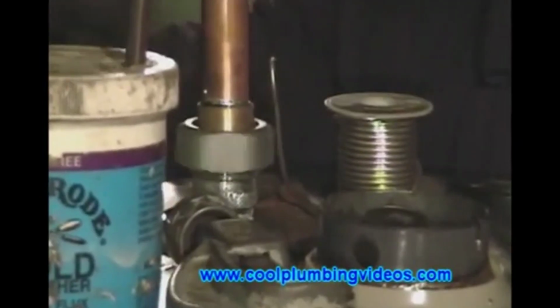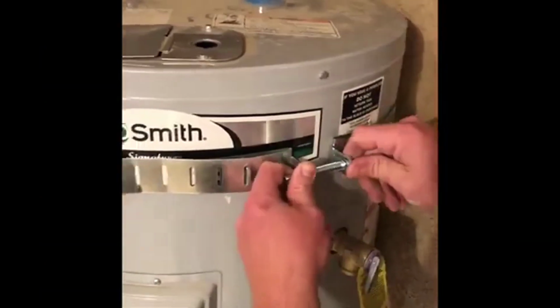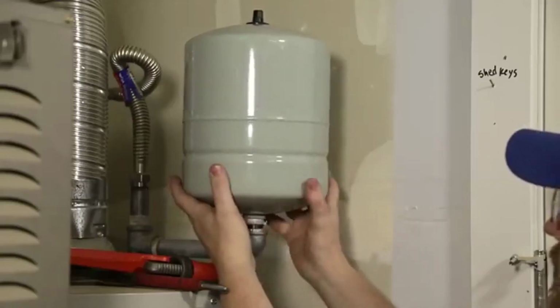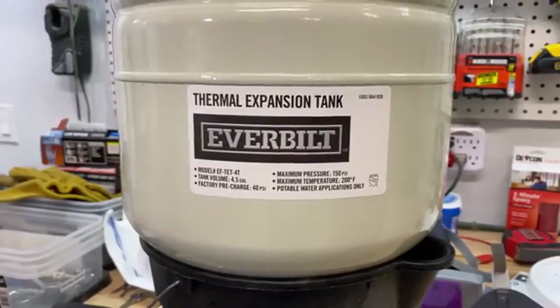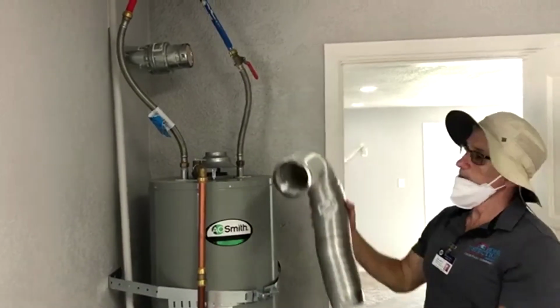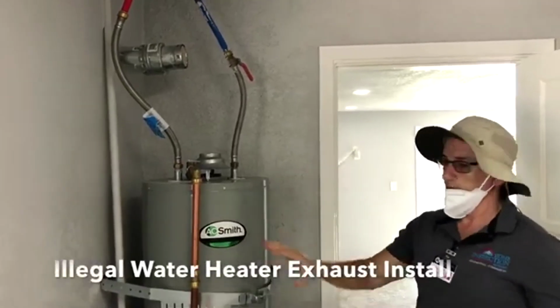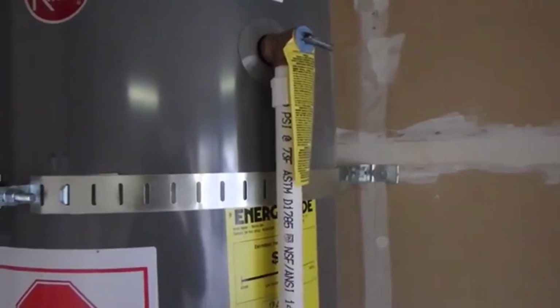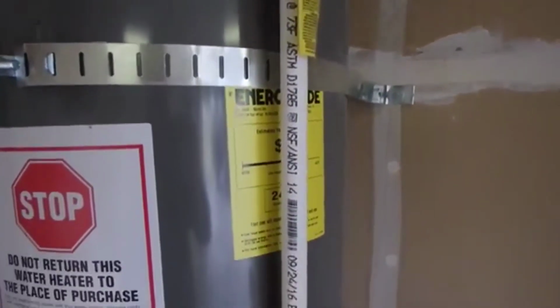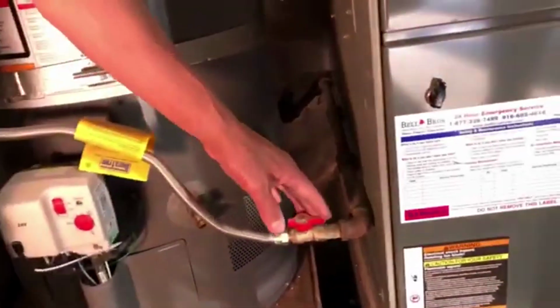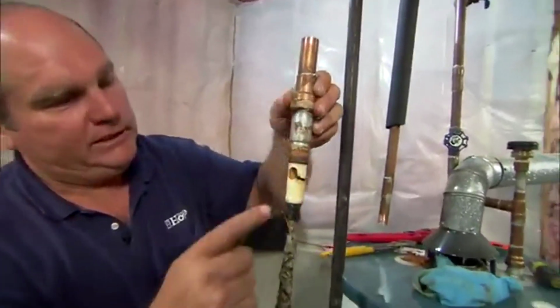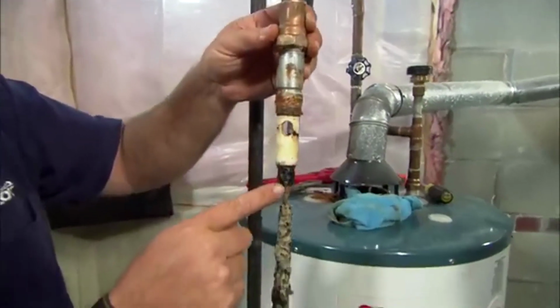And yes, I know this sounds minor, but here's the problem. Water heaters have a standard service life of about 8 to 12 years. If yours is older than that, inspectors note it and buyers notice it. But the bigger issue is the installation details. Missing a seismic strap in earthquake-prone areas. No expansion tank on closed-loop systems where one is required by current code. The pressure relief valve discharge pipe terminated incorrectly. These are the small installation details that inspectors flag and that make buyers feel like the house was put together carelessly. A lot of these are $40 fixes. Do them before the inspection.